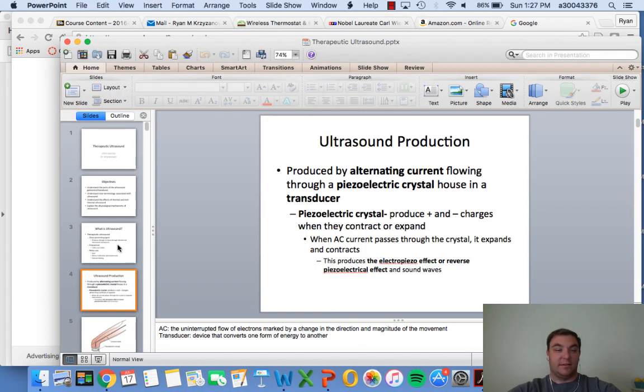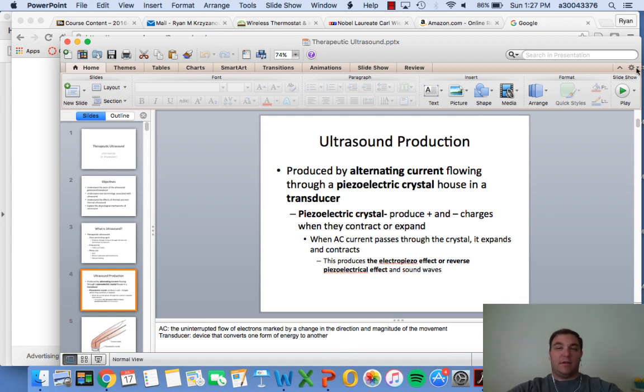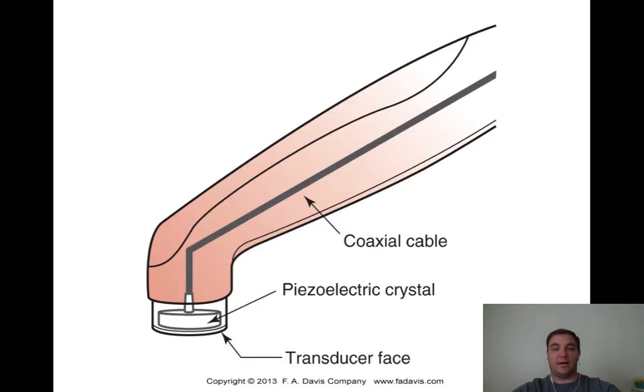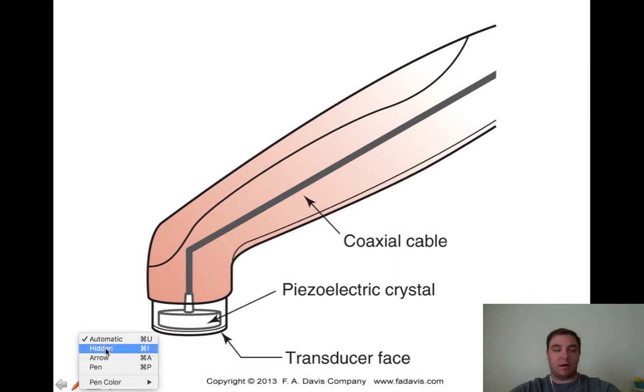AC is the uninterrupted flow of electrons marked by a change in direction and magnitude of movement. The transducer is the device that converts one form of energy - electrical energy from the wall - to sound energy. The coaxial cable goes down the wand and connects to the generator of the machine. Within the wand, we have the piezoelectrical crystal that changes and deforms producing the sound wave. The transducer face is what gets rubbed on the patient's skin with a coupling medium.